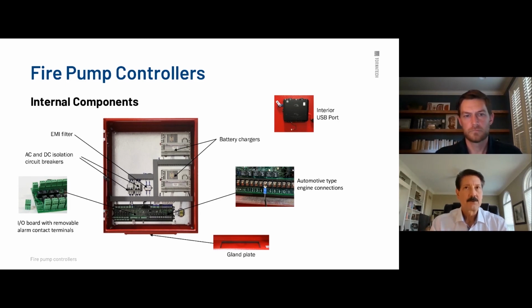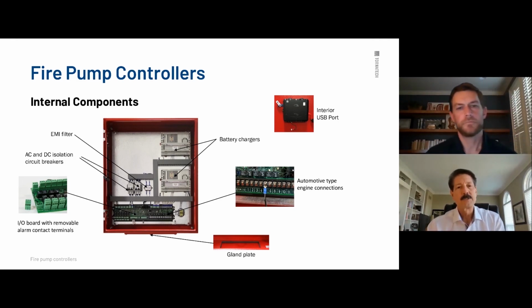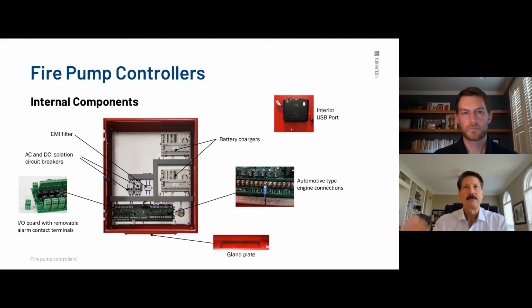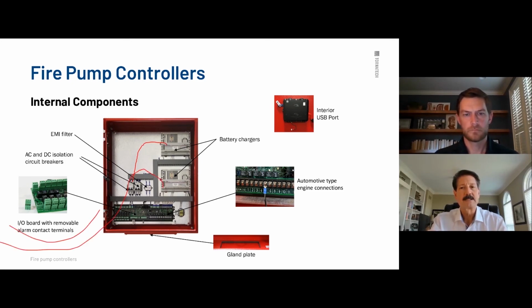And again, that diesel controller has two jobs. Number one is when the pressure drops below cut in, it turns the engine on because it thinks there's a fire. Number two is there's chargers. We need to maintain the battery charge itself. And 13.8, you know, is awesome. Anything below 12.8 or something, your batteries are at risk, and if your amperage is below 1 amp, there's an issue there too. Now, from the chargers, we go through a DC breaker, 2 DC breakers out to both of the battery banks themselves.